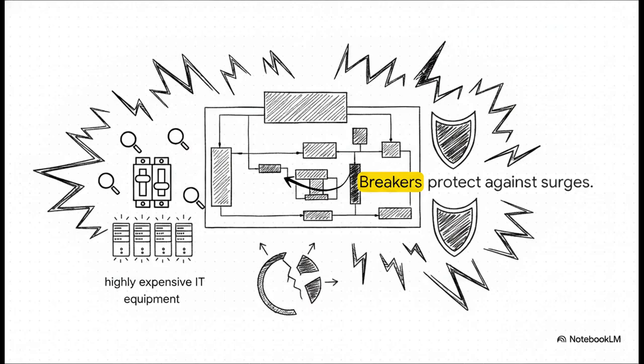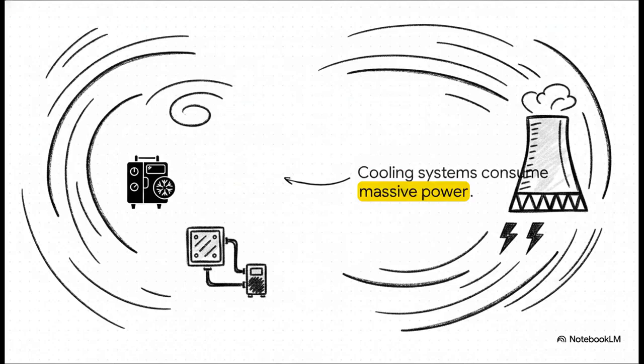from surges or faults. Monitoring at the breaker level is vital because it lets you identify localized hardware risks before they can take down a whole cluster. But hey, we absolutely cannot forget this incredibly crucial piece of the puzzle, the cooling systems, or CDUs. The IT equipment isn't sitting in there alone. High-density AI GPUs get incredibly hot, and the liquid cooling systems, pumps, and cooling towers required to keep them running, well, they consume massive amounts of power themselves. This represents a completely distinct and totally vital tracked asset class in our infrastructure journey.